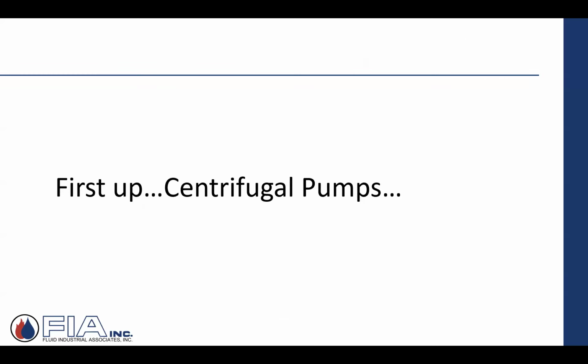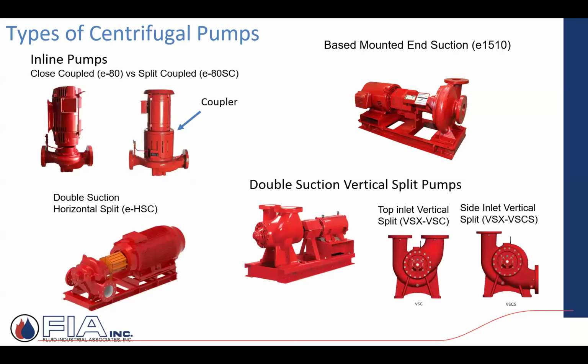So the first component out of hydronic system components, first up, I should say, would be centrifugal pumps. And when you say centrifugal pumps, and you're getting into this hydronic world or engineered world, if you will, we've got all different styles. They all fall under the family of centrifugal. We'll throw up a couple of quick definitions of centrifugal pump, but descriptions: inline pumps, close coupled, split coupled. Inline meaning the volute itself is sitting in line with the piping. There would be piping on either side, and I've got some details we'll show afterwards, but it's technically in line with the piping that the pump is installed.